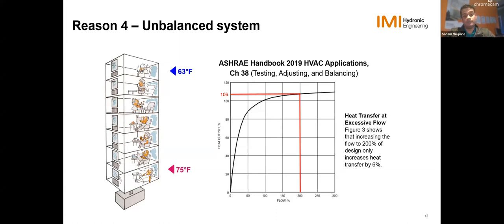So you're pumping twice as much water all the time in your system, and all you're getting is 6% higher heating or cooling output. And that's a lot of energy being wasted for something that's not even enough to make you feel any kind of changes. But in the background, you see you're wasting a lot of energy pumping that water. So that's exactly why we want to avoid unbalanced system, and we're going to deal with that today and look at what are the ways we can properly balance a hydronic system.